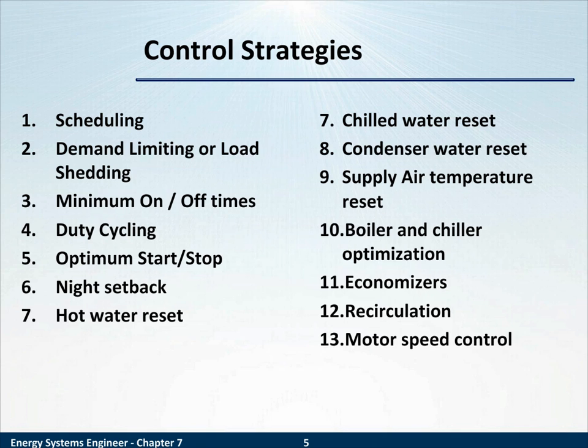The idea of optimum start and stop involves tracking heat loss or heat gain during off hours, and alongside of that, tracking outside air temperature. And with that data, determining optimum shutdown and startup to minimize energy. However, doing so while maintaining comfort during business hours. We addressed in a previous chapter that if you make changes and negatively impact the people inside the building, you have cost much more than the energy savings can justify.